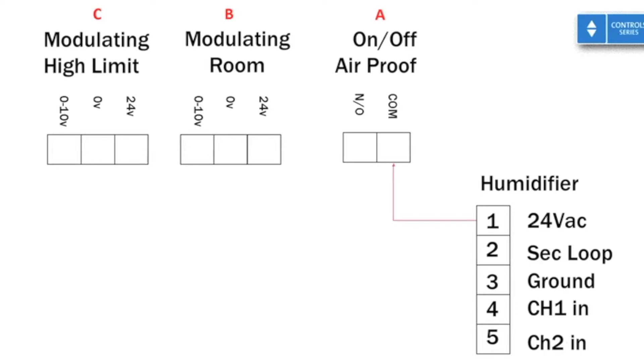This is the first control loop explored earlier. 24 volts leaves the humidifier on pin 1, reaches the common pin of the air proving switch, and when there is airflow, the device closes the connection across the common and the normally open contact, which is then wired back to pin 2 — the return for the secondary loop. A relatively simple circuit.